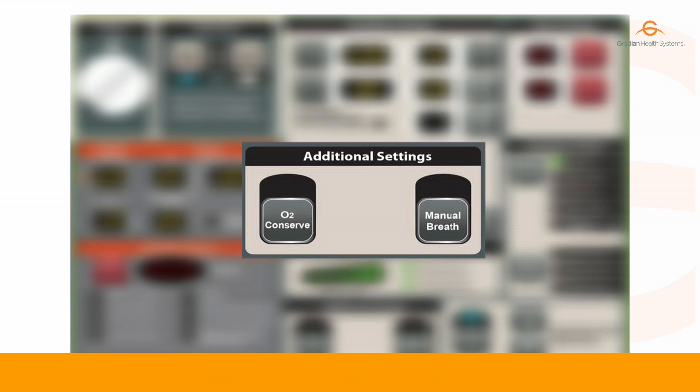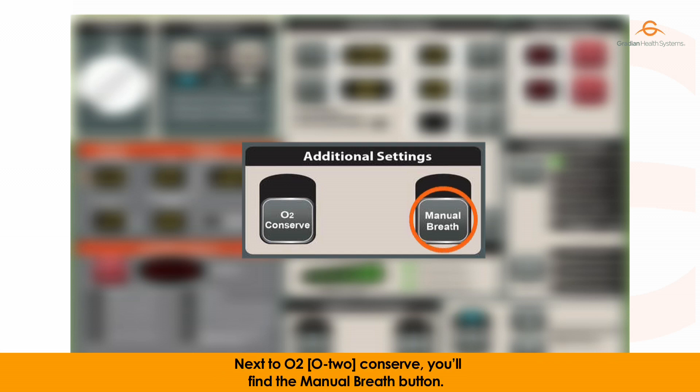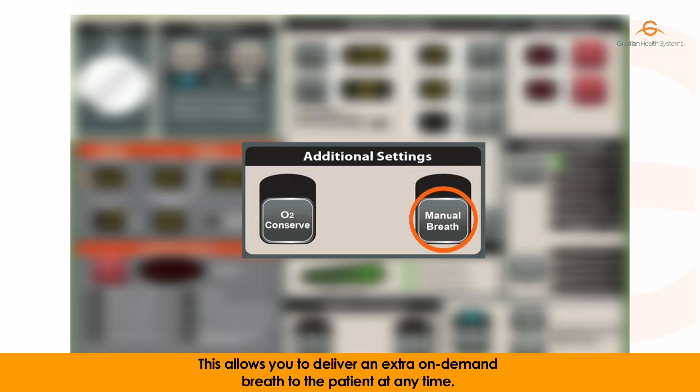Next to O2 conserve, you will find the manual breath button. This allows you to deliver an extra on-demand breath to the patient at any time.